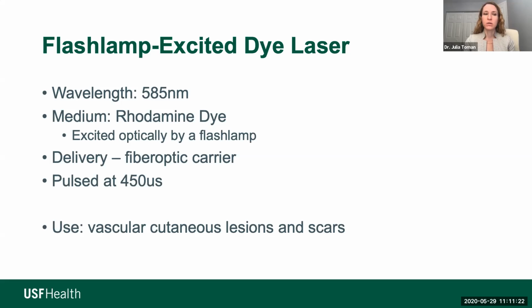It again utilizes a fiber optic carrier and is pulsed at 450 microseconds. And this pulse time is based off of the thermal relaxation time of ectatic vessels found in benign vascular cutaneous lesions. So its use is mostly for these particular types of lesions.